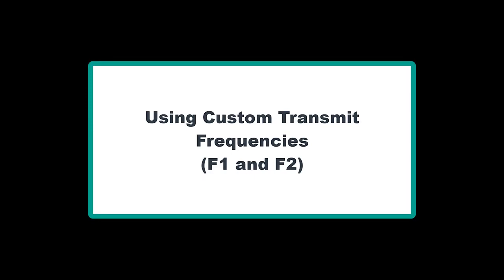If necessary, you can change the transmit tone frequencies to meet your testing requirements. Any change in either frequency 1 or frequency 2 will require a recalibration. Once those frequencies are changed, moving between low and high IM bands will result in frequency 1 and frequency 2 being reset back to the defaults. Because of this default behavior, it is easiest to save a setup for each frequency configuration you want to test.